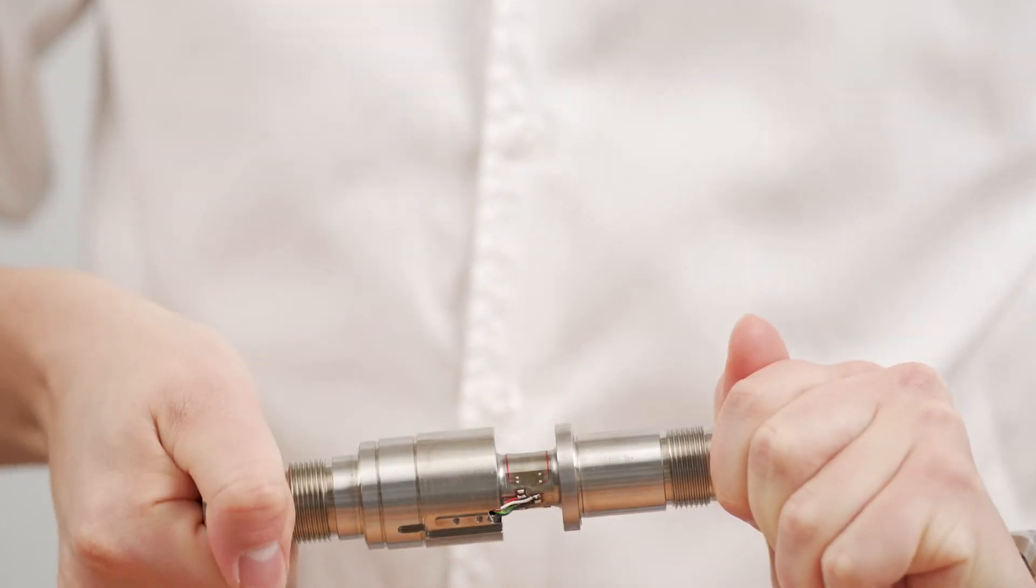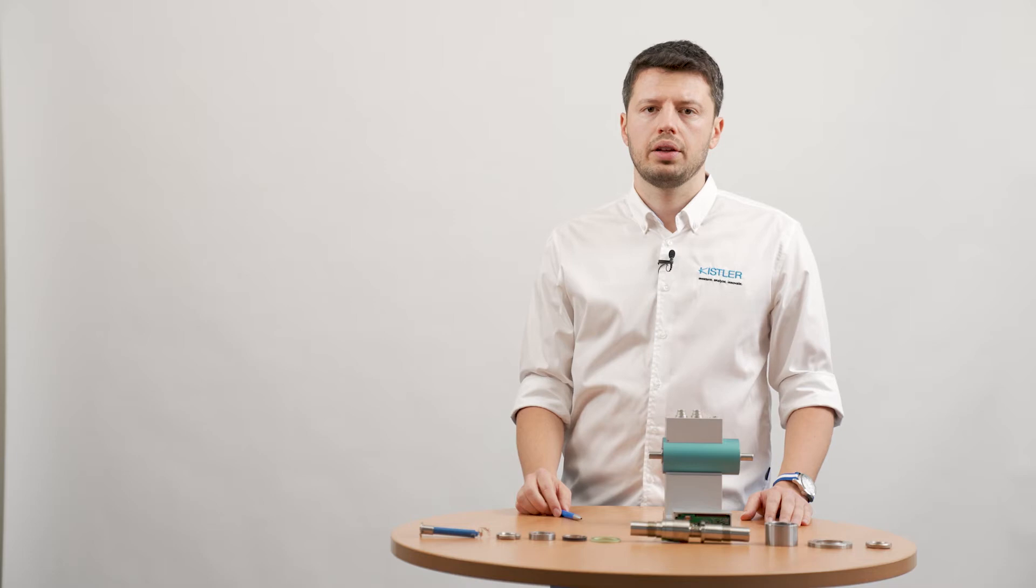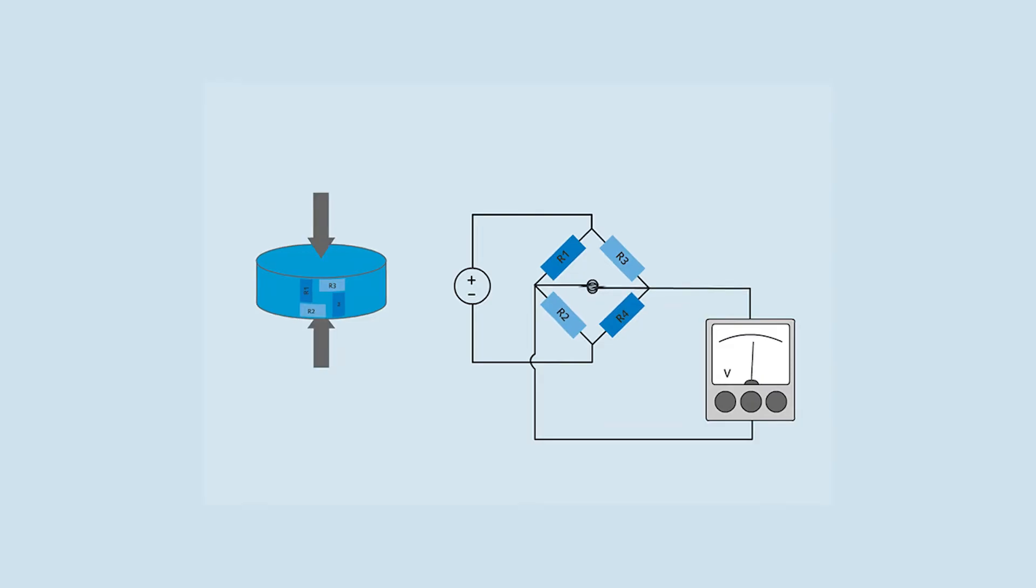If a torque is applied to the measuring shaft, two strain gauges are always stretched and the other two compressed, causing the resistance of the strain gauges to change in opposite direction. From this change in resistance the elongation of the strain gauges and thus the acting torque can be derived.